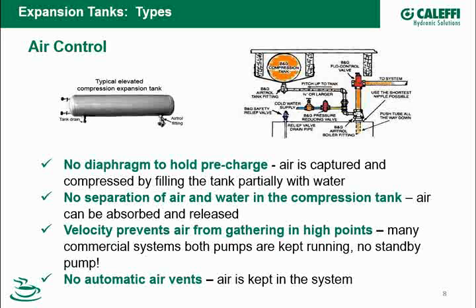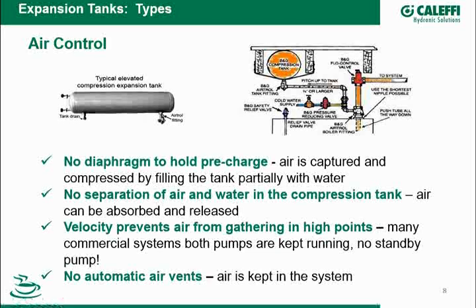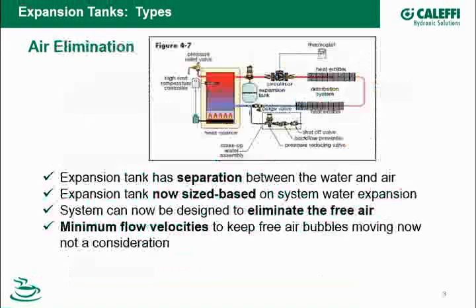It's been around before the pre-charge expansion tank. It still exists in existing systems, and once in a while I run across an engineer that's still designing air control. Now, the diaphragm expansion tank. It's associated with the air elimination system. I say diaphragm, it could be bladder. So in this tank, I'm going to have a diaphragm or a bladder that separates the air and water. The first big benefit for me is I don't have to size based on the tank being partially filled with water.